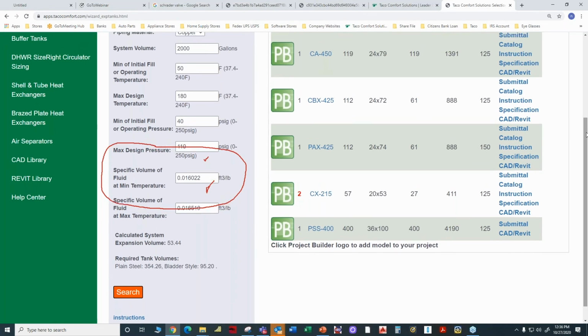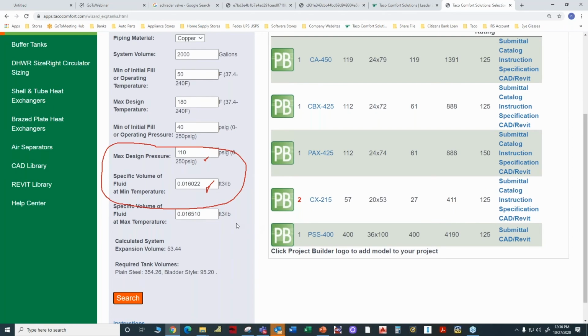There it is. With those two values and the volume of the system, the software has calculated how much the water will expand. And in this example, it'll expand approximately 53 gallons. So kind of keep that number in the back of your mind. If we were using a plain steel tank, we'd have to have a plain steel tank that had a minimum volume of approximately 354 gallons.